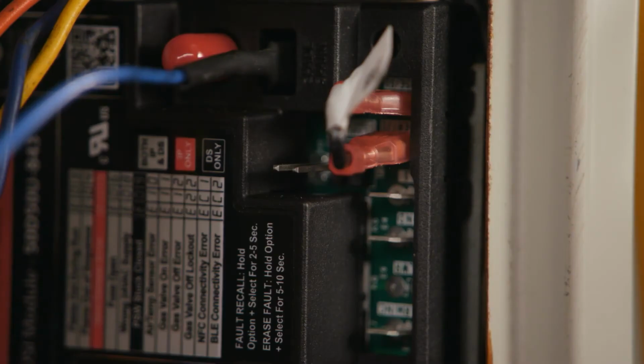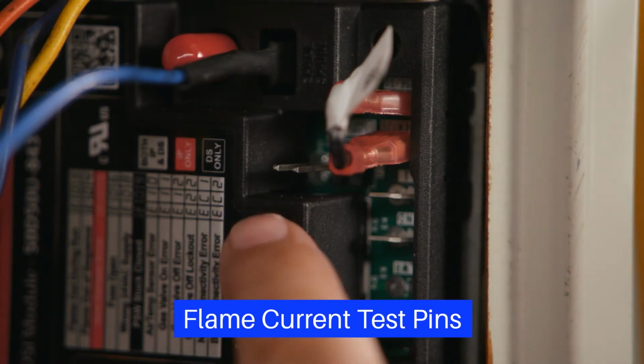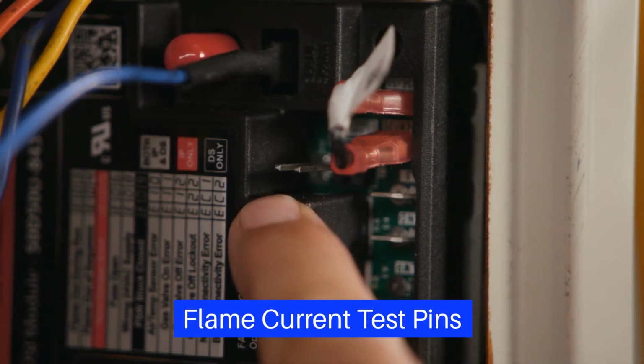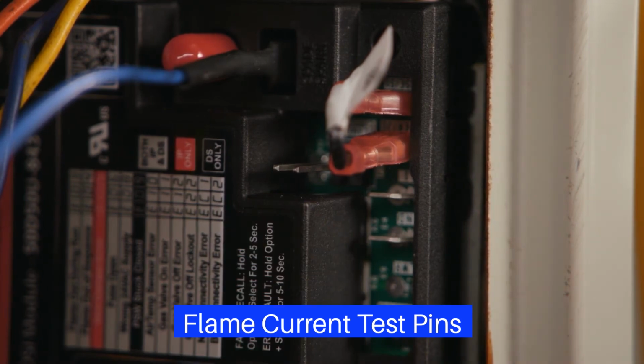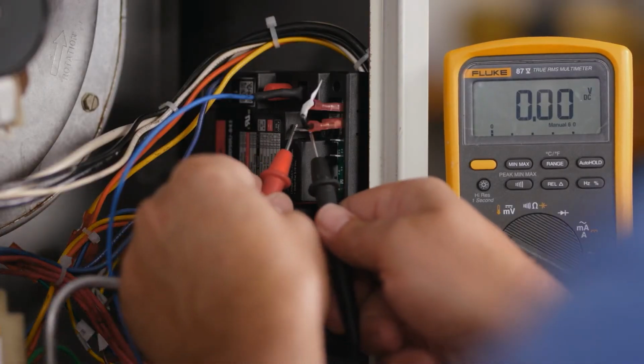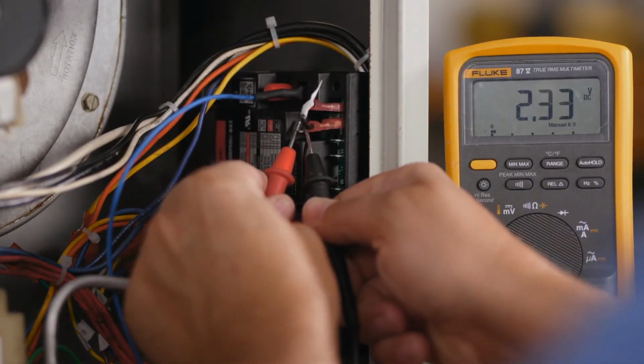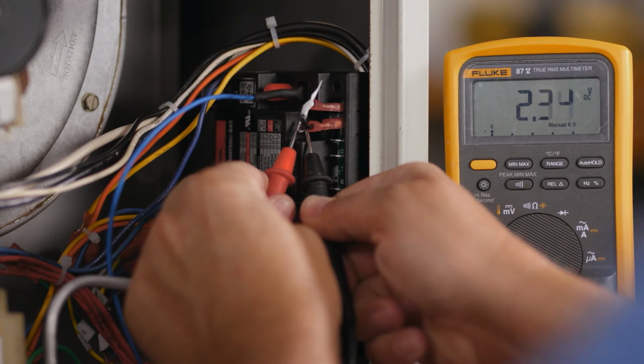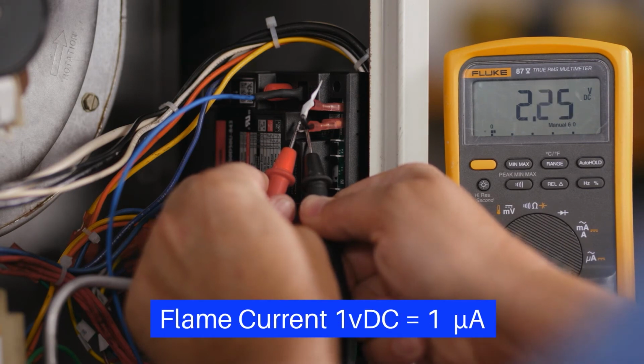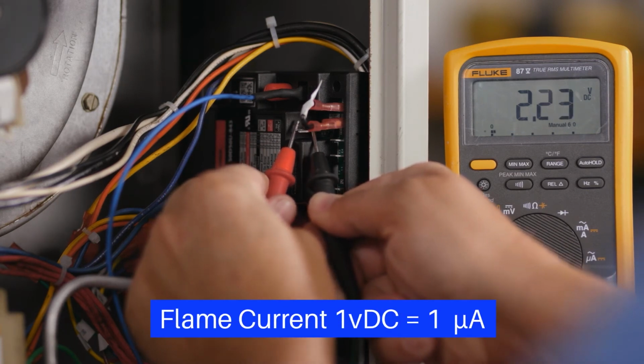The 50D50U-843 comes with flame current test pins. These pins are easy to access and provide the flame current reading. To test the flame current, set a voltmeter to DC volts and measure across the pins while a flame is present on the sensor probe. 1 volt DC equals 1 microamp.